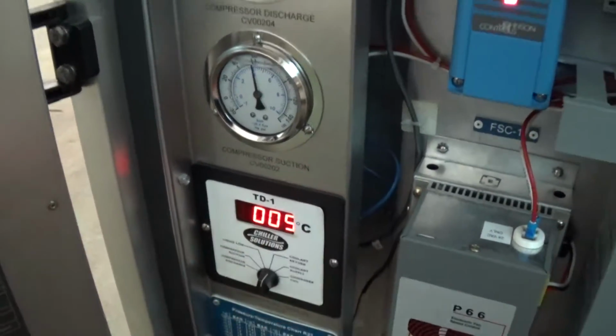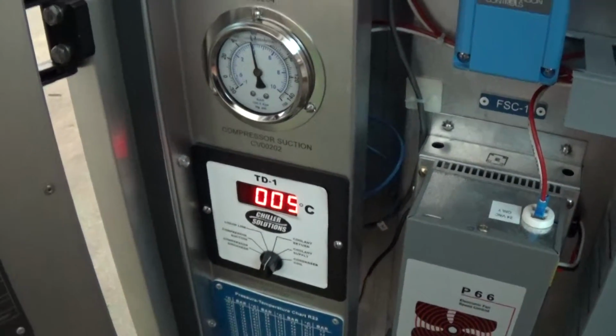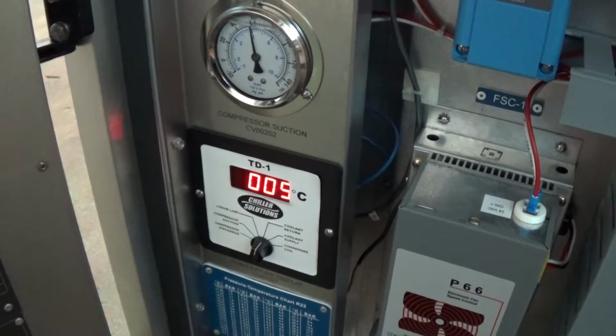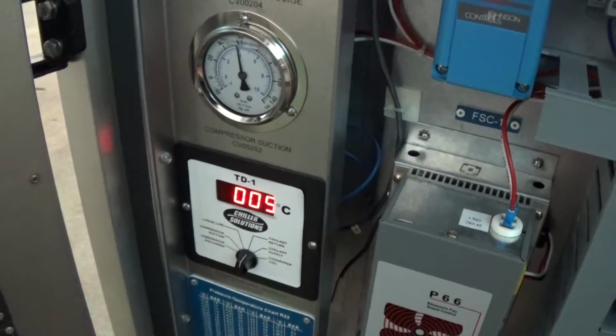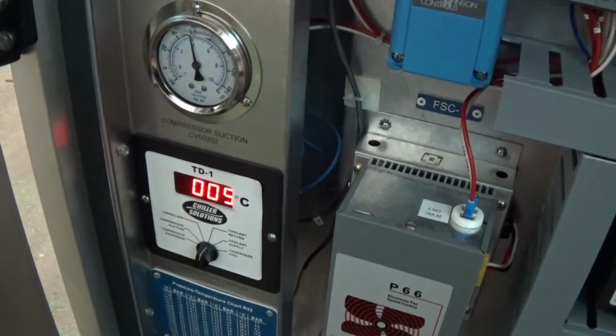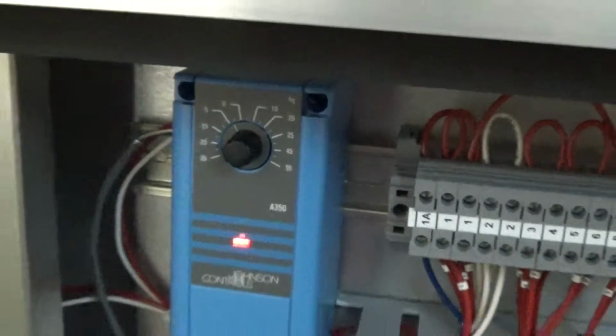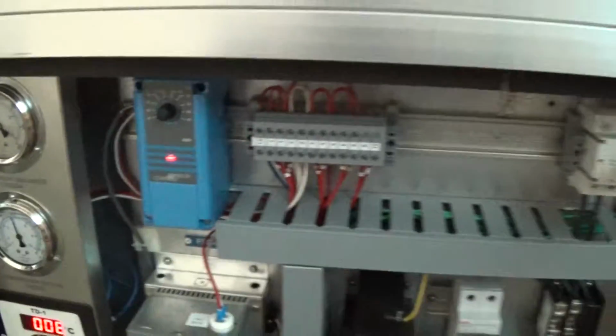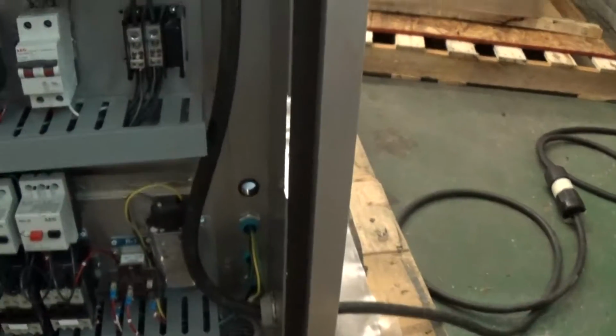So again, we want to run this down and maintain minus 2 degrees centigrade, which is about 28 degrees Fahrenheit. And we may have to tweak that adjustment a little bit when we're doing that. So this unit, our incoming power, it's single phase. We're just using our own cable right now. Okay, it's single phase, so we don't have to worry about rotations. You have a ground right here, and then you just have your two hots.